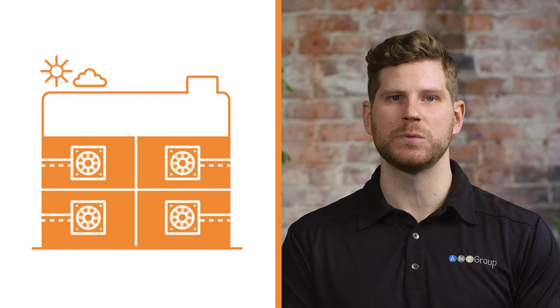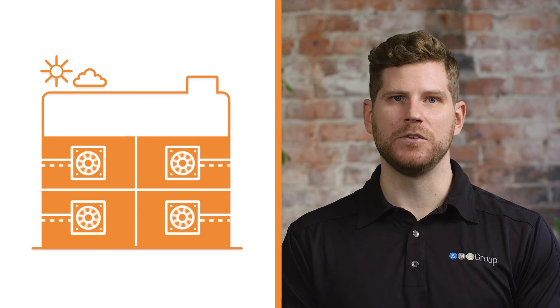A decentralized ventilation system uses a number of small, dedicated HRV or ERV units, each serving a single individual suite within the building. Each suite has connections to the HRV through supply and exhaust terminations on the exterior of the building, as well as a small network of supply and exhaust ducting within each suite. Because each HRV unit has its own dedicated suite, it's easy for the ventilation to be increased through a switch or controller by the occupant.